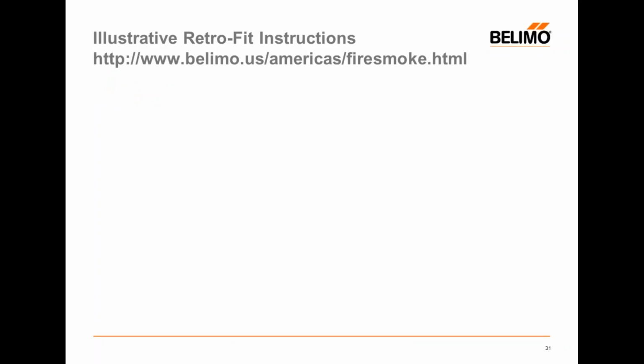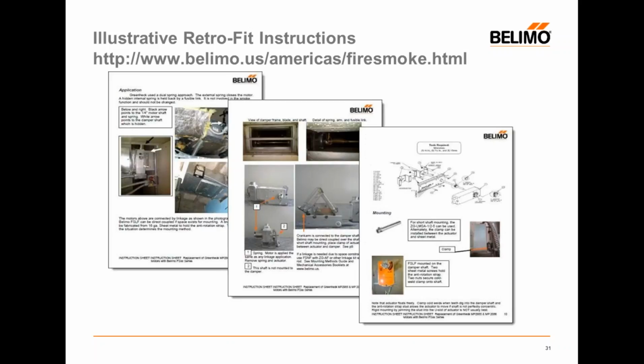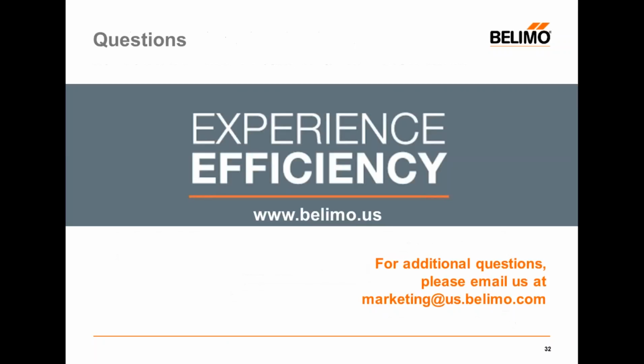One thing Belimo has done regarding fire smoke damper actuator replacement is put together a comprehensive list of retrofit instructions that you can find on our Belimo.us Americas Fire Smoke portal. As you can see, we have step-by-step instructions for replacing fire smoke damper actuators on all fire smoke damper assemblies made by the major manufacturers of fire smoke damper assemblies.